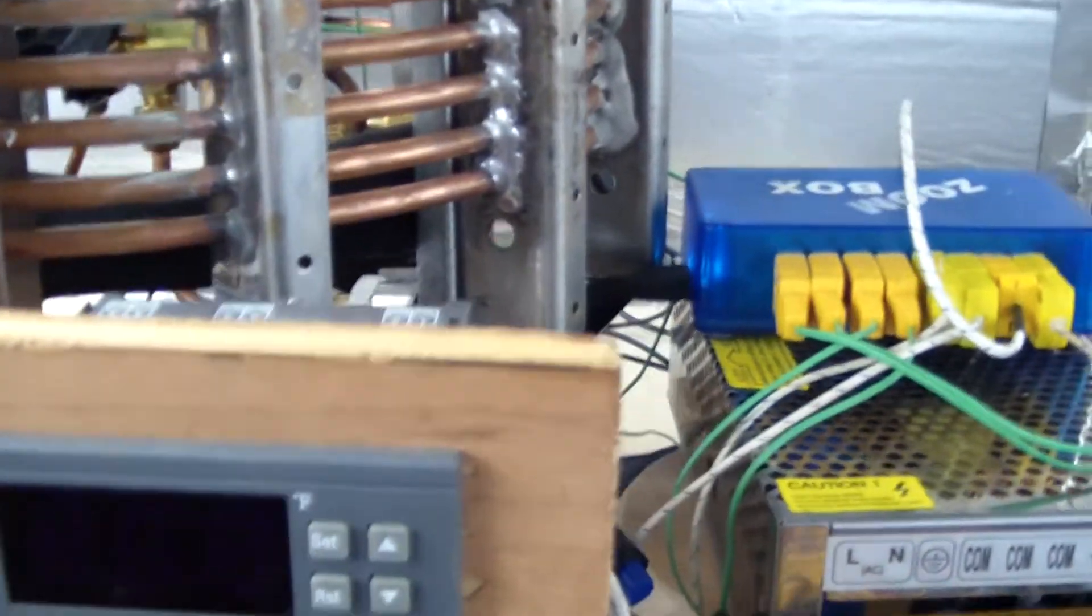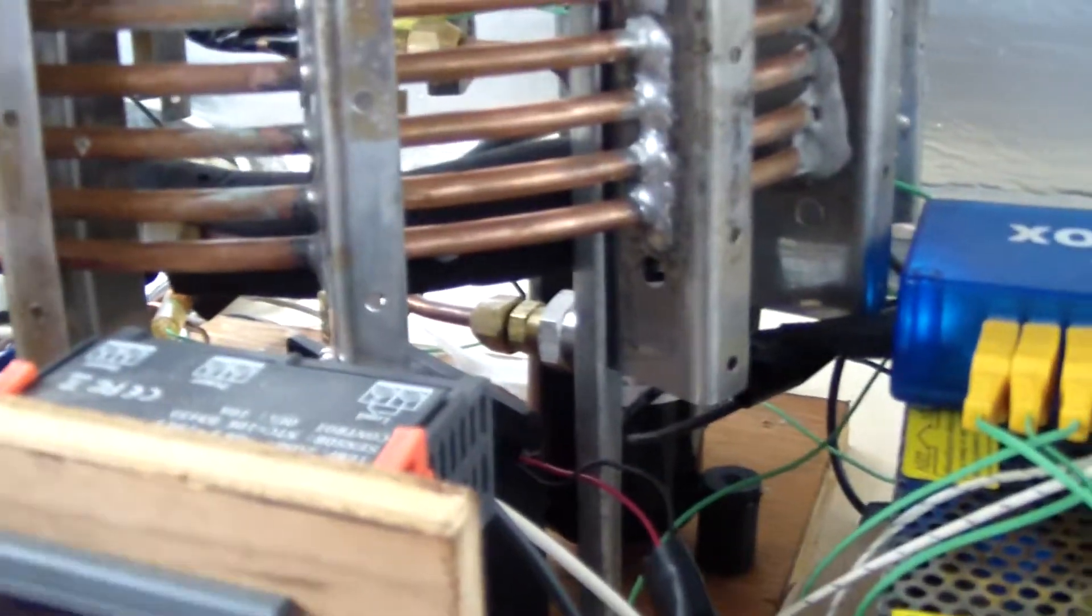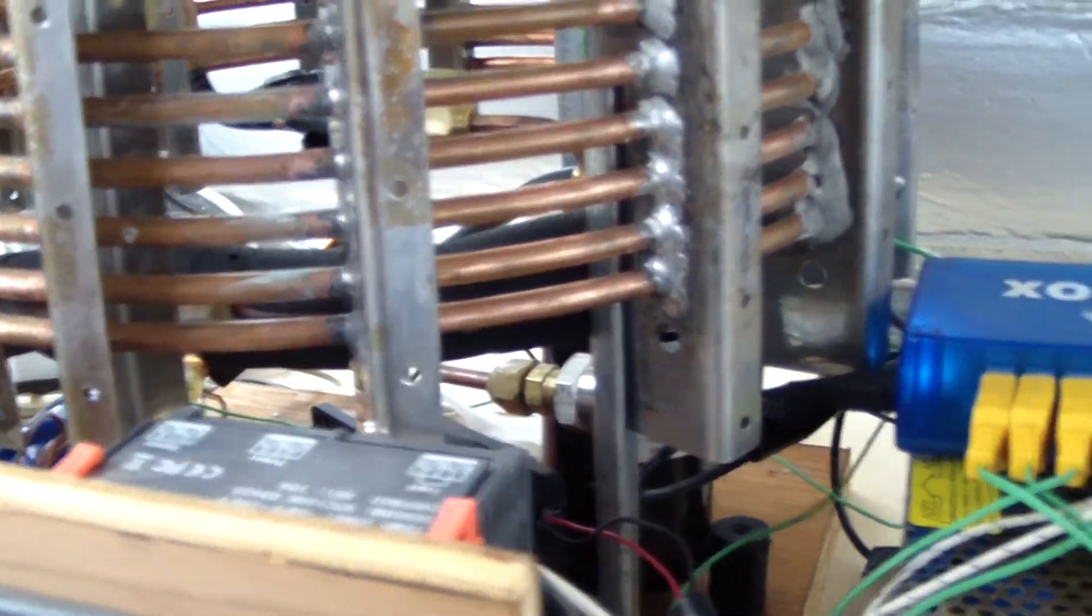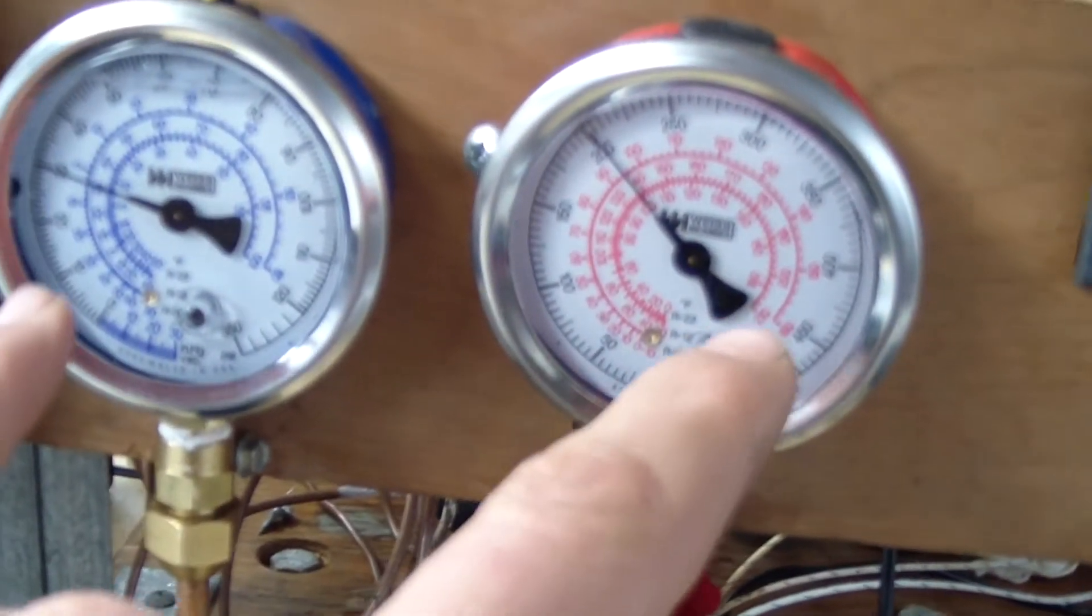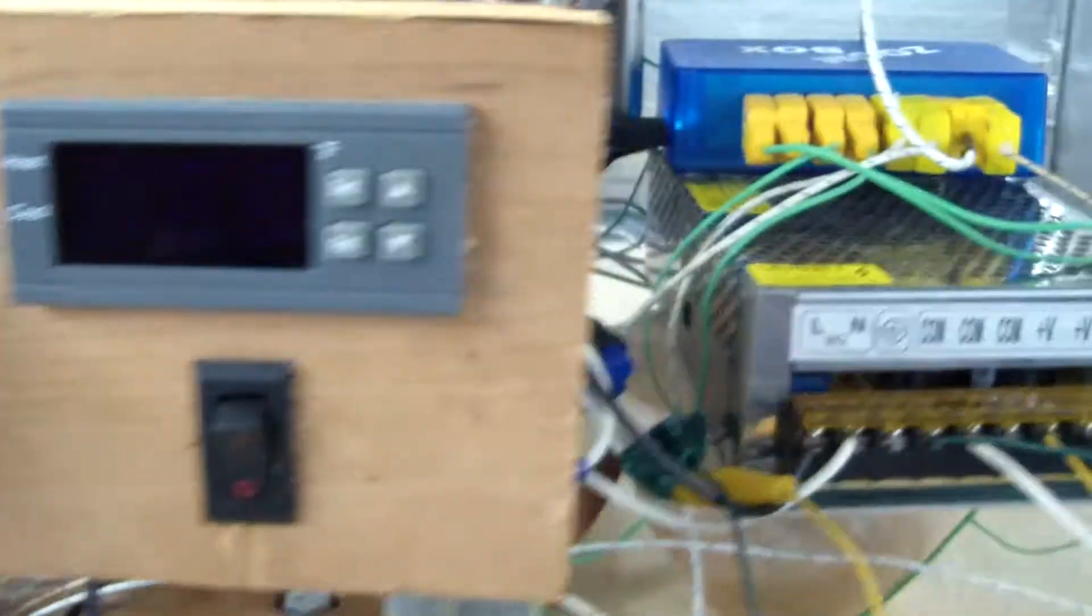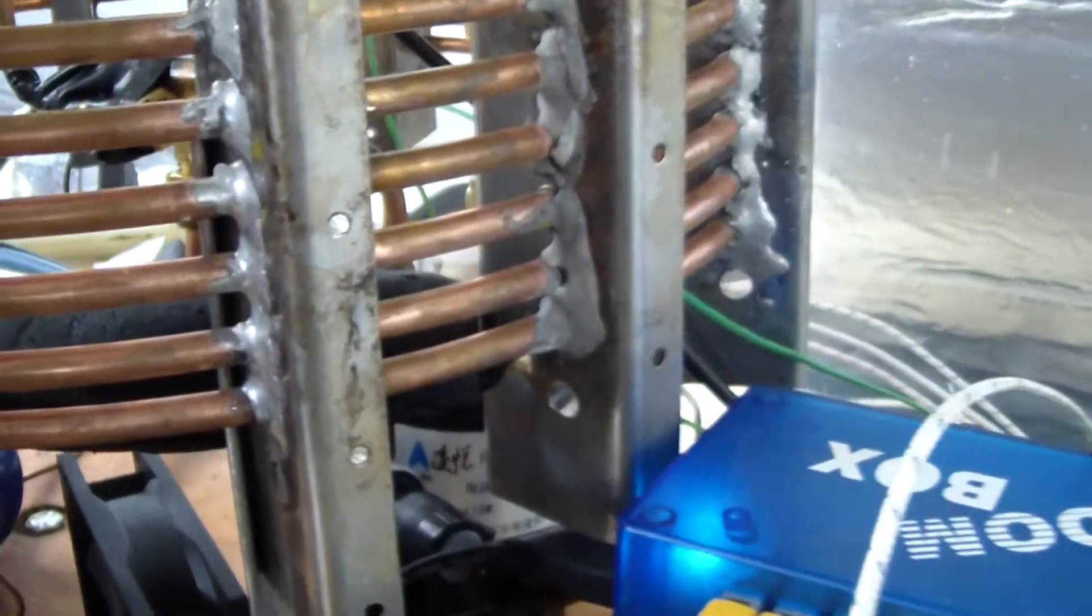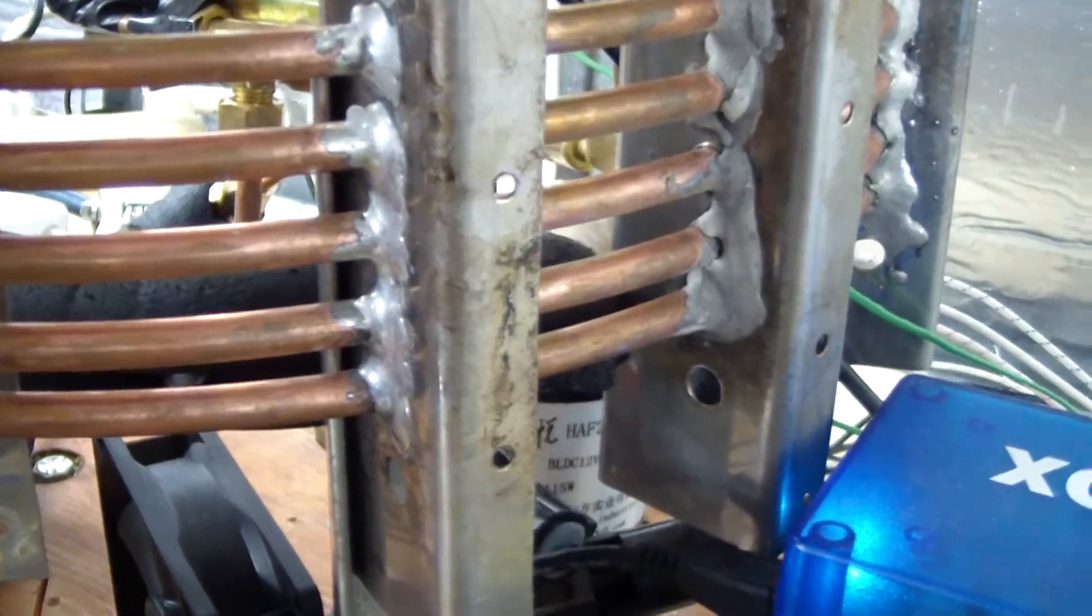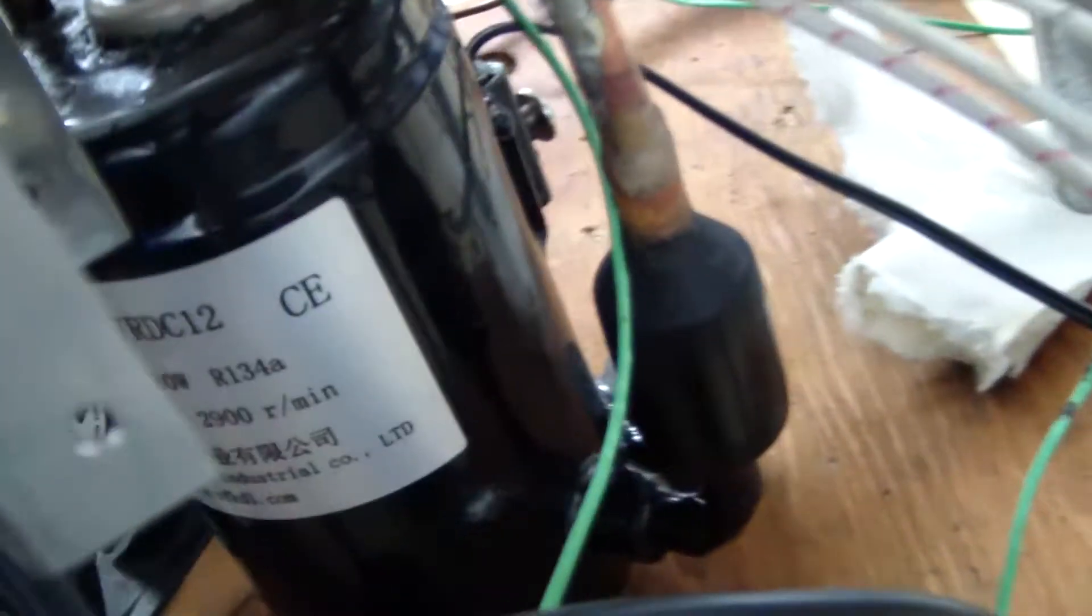So normally when a compressor shuts off with a cap tube like this, at least a reciprocating compressor, the pressure equalizes through the cap tube. And what happens with this one is it will start to squeal and whistle. I don't know how much you can hear that.